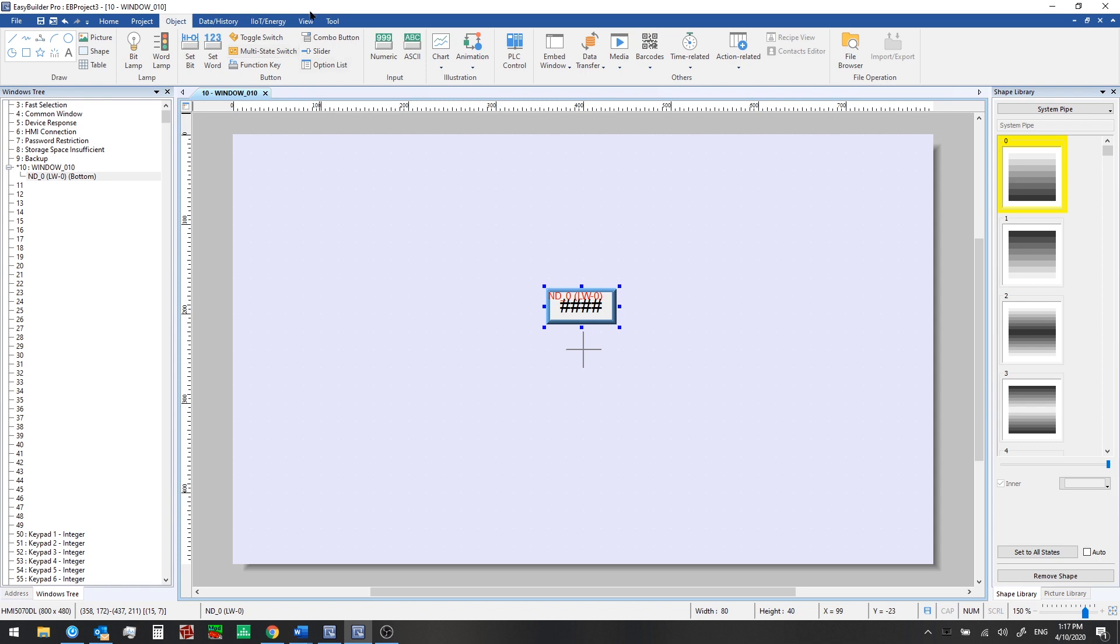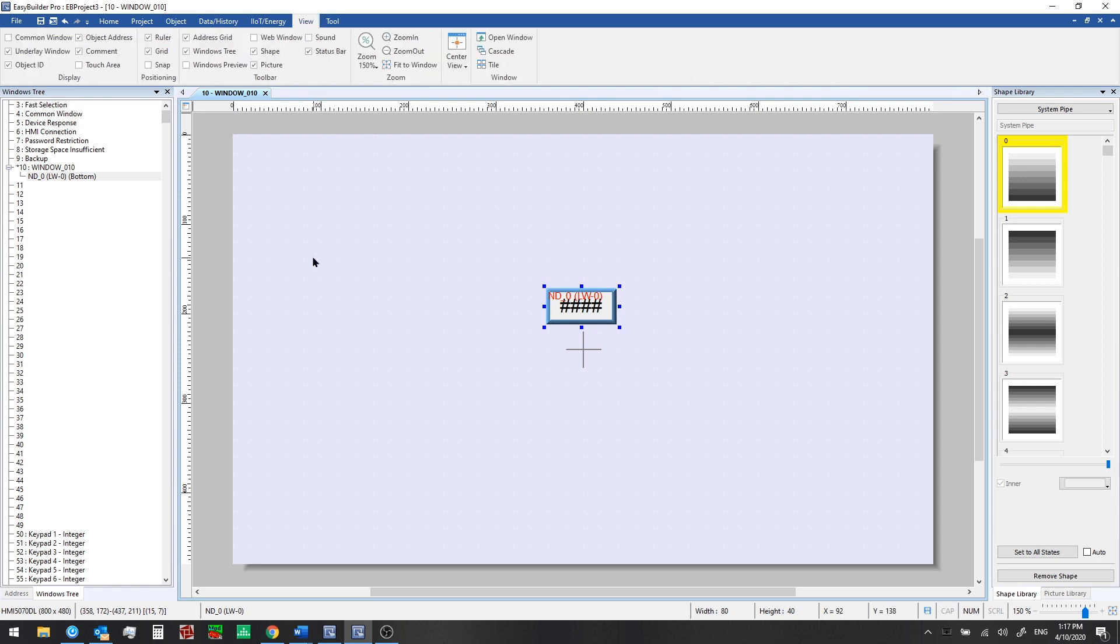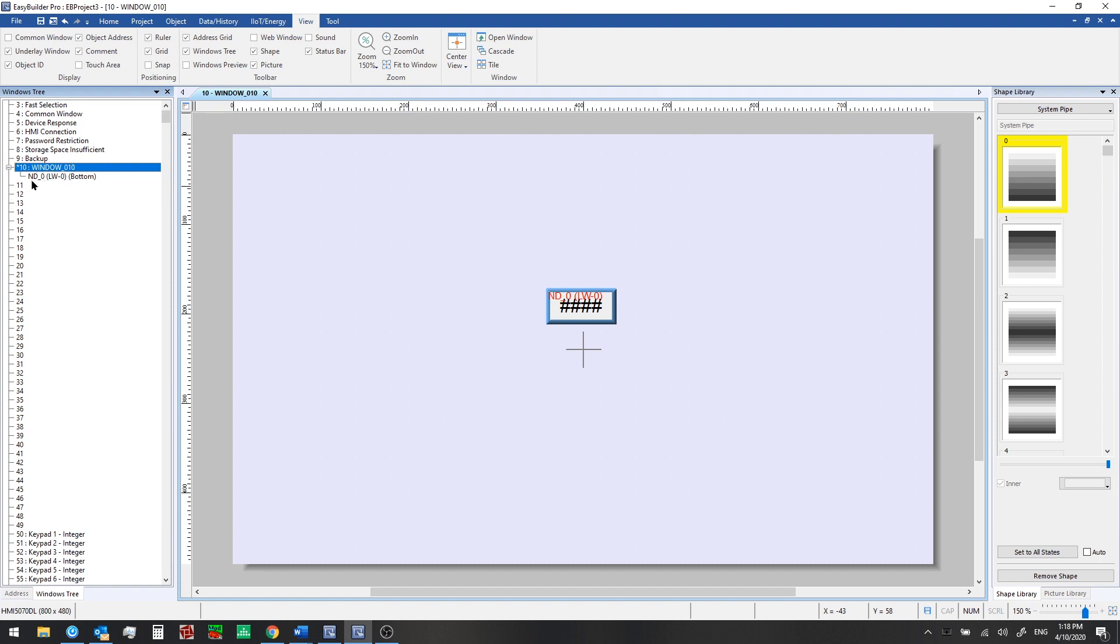If we look at the view tab, let's toggle some of these in the display area. So object address is the first one. If we uncheck that, then we see this red text disappear or reappear. LW0. So that's telling us local word zero is the address that this object is reading from. If we toggle object ID, we see it hides this ND0. That stands for numeric display. If we look in the window sidebar now too, we also see that ND0 and the address LW0. So that's all we need to be able to display a value that is numeric on the HMI itself.